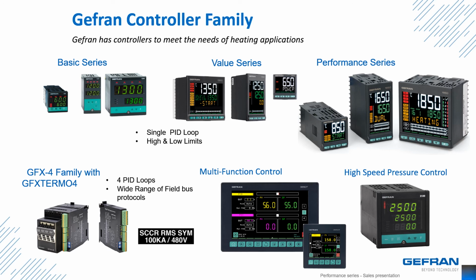In the upper left is our basic series. The biggest thing to notice is the LED display. It also has fewer programming options, but is a good solid controller. In the lower right is our high-speed controller, the Model 2500. Because of the high speed, it's suitable for fast-acting systems such as closed-loop melt pressure control in an extruder. It can also be set for control of roller tension control.